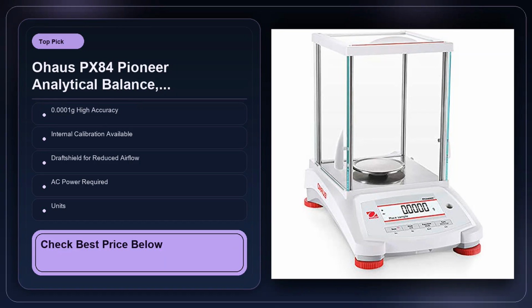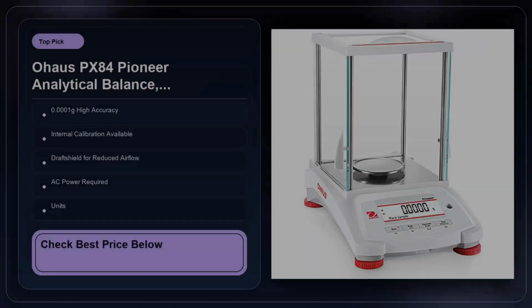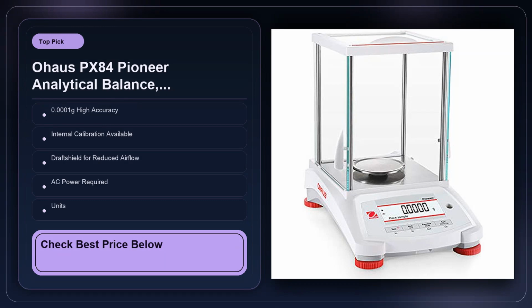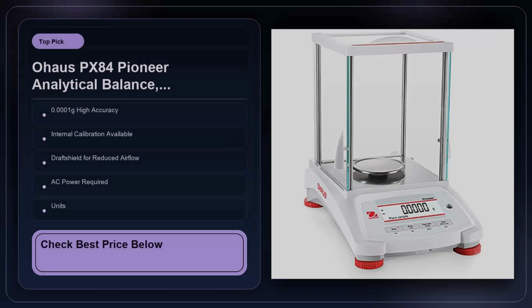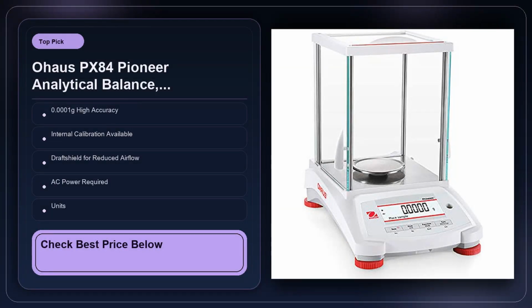The Draftshield on the PX84 is a double-edged sword. On paper, it's a lifesaver because it blocks air currents that would otherwise sway a 0.0001g measurement. In practice, I've seen the shield get in the way when you need to quickly add a solid or a liquid droplet. You have to lift the shield, place the sample, then close it again. Each movement adds a few seconds to the workflow. For a high-throughput environment where dozens of weighings happen per hour, that extra handling can add up.